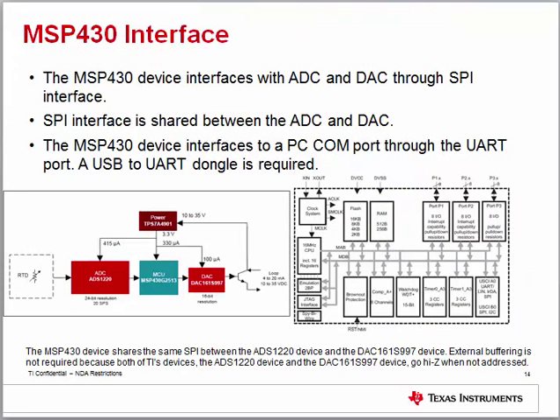The MSP430 in this application records raw ADC codes from the ADS1220 device corresponding to temperature readings, applies offset and gain calibration, converts ADC codes to resistance values, performs linear interpolation to overcome RTD non-linearity, converts temperature from the lookup table to a DAC current value, and then applies the equivalent code for the loop current to the DAC device via SPI.